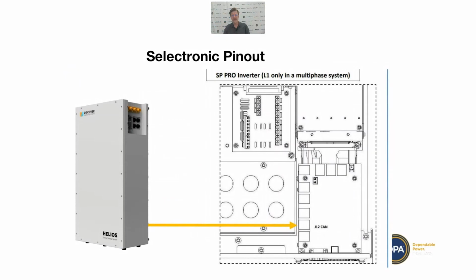Once you've connected the CAN bus and it's started reading it, it won't operate unless, if you take it out again, you completely shut the system down and boot it up again. So again, like Victron, you want to set the off-grid settings for the Selectronic so that if it does completely go down and come back up without comms, it's got the correct settings. But it's much easier with Selectronic because of the way we're going to commission it. So, CAN bus cable from there into there - it's reasonably straightforward.